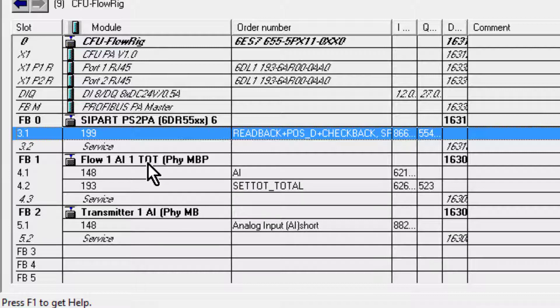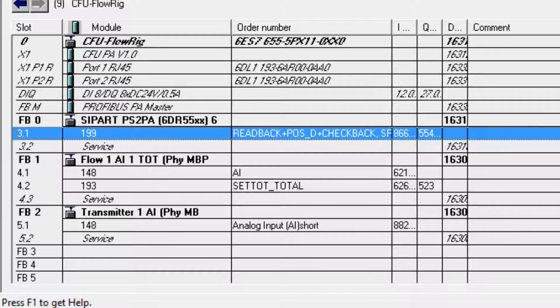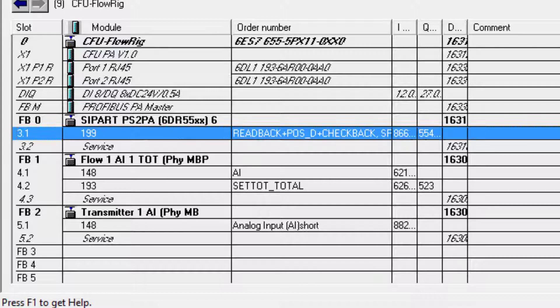So all I need to do now is put that into my project in the usual way using the mon analog block and bringing the data back. I'm not doing anything else to bring back the diagnostics from the instrument - that's all done via PDM and it's an offline configuration.